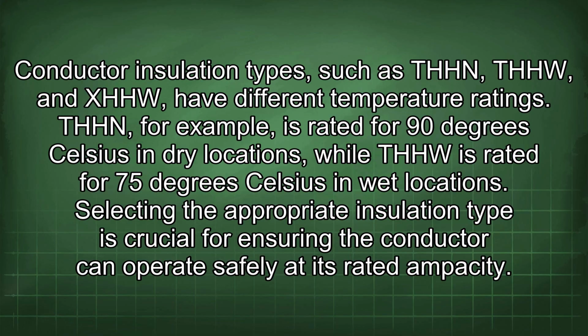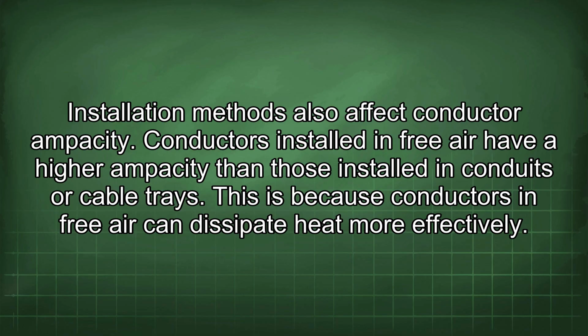Selecting the appropriate insulation type is crucial for ensuring the conductor can operate safely at its rated ampacity. Installation methods also affect conductor ampacity. Conductors installed in free air have a higher ampacity than those installed in conduits or cable trays. This is because conductors in free air can dissipate heat more effectively.